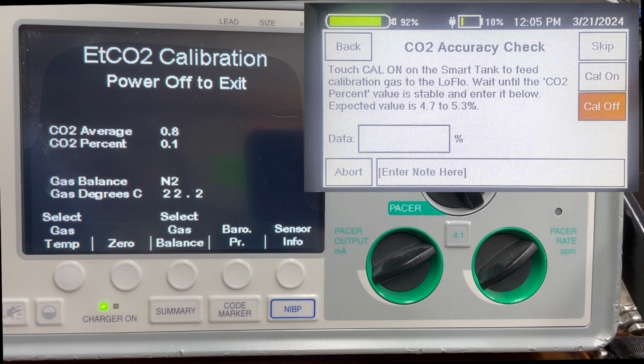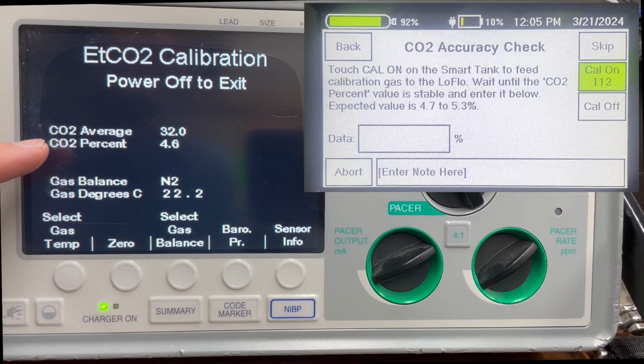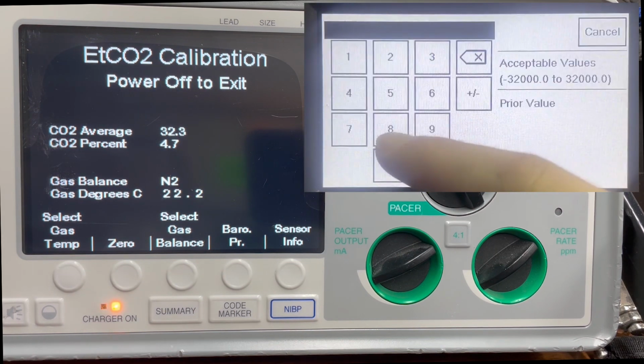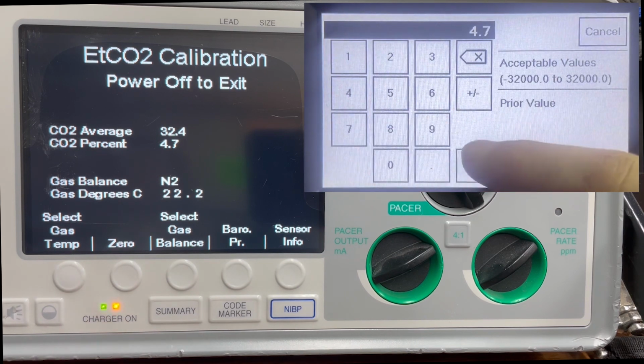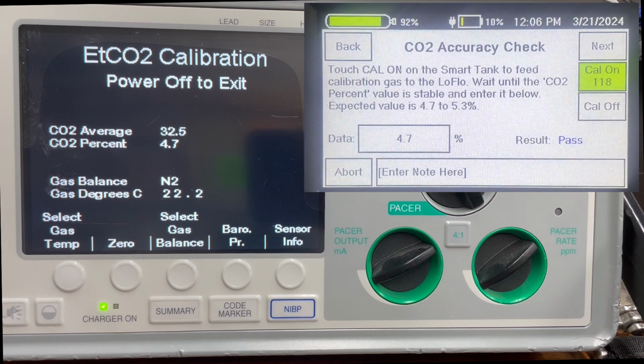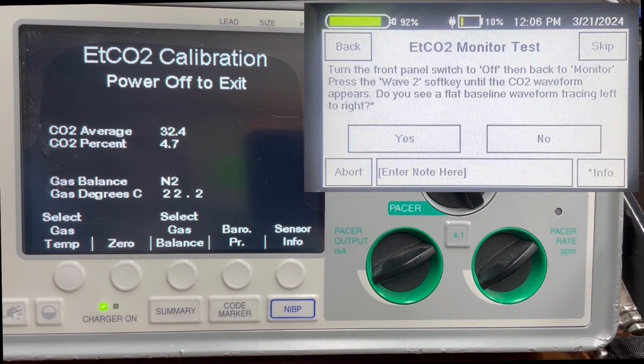Our next step will be the CO2 accuracy check. It's going to want us to click the Cal On function here, delivering calibration gas to our defibrillator. What we're looking at over here is the CO2 average and the CO2 percent. We want that CO2 percent to read between 4.7 and 5.3. So we'll let that balance out. You can see that CO2 percent settling at about 4.7. So we'll plug that into the Smart Tank right here, 4.7%. Letting us know that we've passed our accuracy check. Click Next to take us to the next step, which is going to be the end tidal CO2 monitor test.